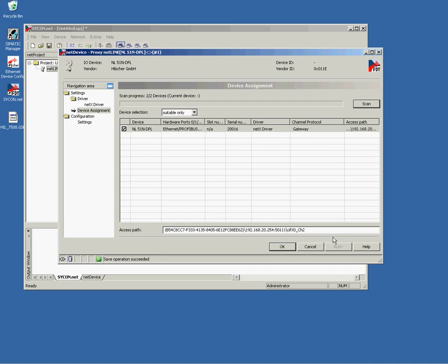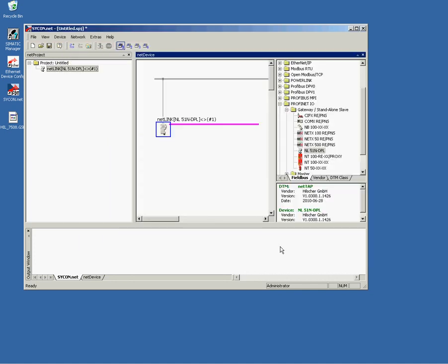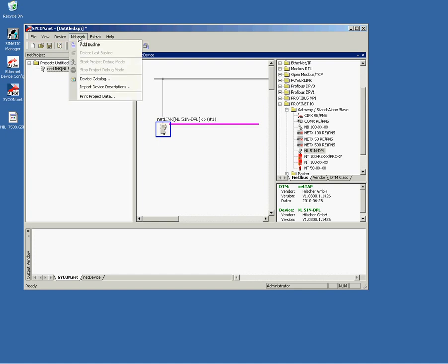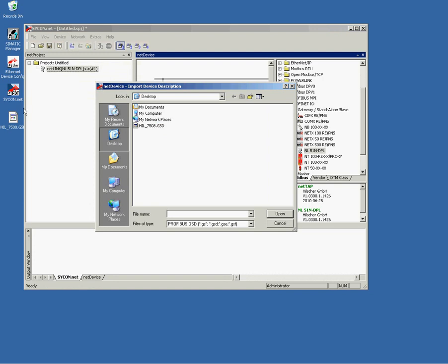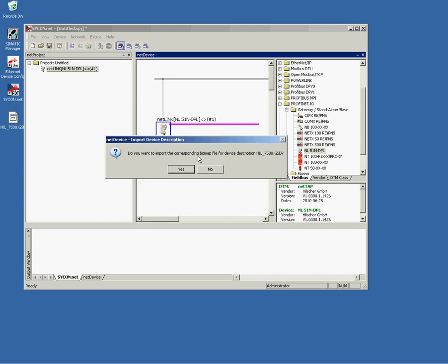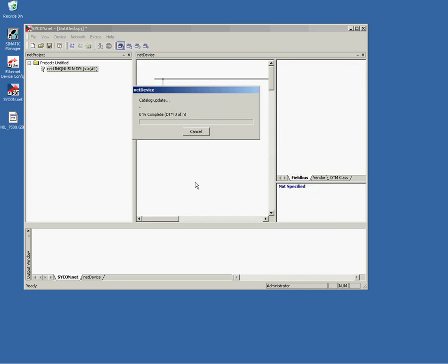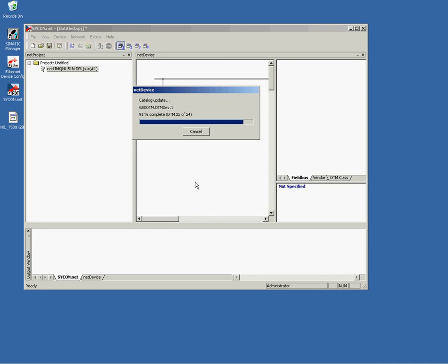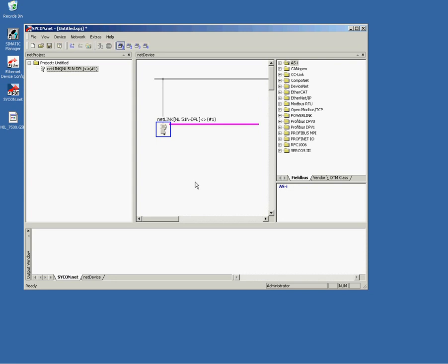Now we can continue with the Profibus configuration. Before we do a network scan on Profibus, we have to import the GSD file of the expected slave first. For this, use the network import device description entry from the top menu. I prepared my GSD file on my desktop. You have to select it. And what Sycon is now doing, it is updating the device catalog. This will take a while. Now it is finished.